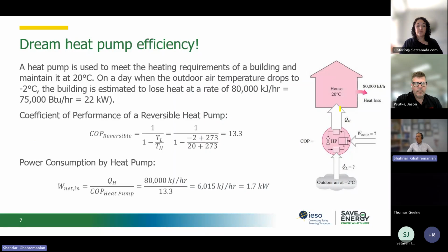From an engineering perspective, if we have a building that requires 80,000 kilojoules per hour, or almost 22 kilowatts of heat, to maintain an indoor temperature of 20 degrees Celsius while the outdoor temperature is -2 degrees Celsius, based on a reversible heat pump engineering calculation, we are going to see a COP, or coefficient of performance, of 13. I will define and show you COP later on, but this is the efficiency of a heat pump.